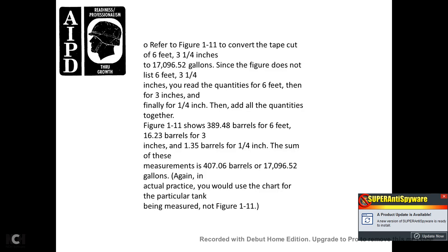Refer to Figure 1-11. Convert the tape cut of 6 feet 3 and one-quarter inches. Since the figure does not list 6 feet 3 and one-quarter inches directly, you need the quantities for 6 feet, 3 inches, and one-quarter inch separately and add them. Figure 1-11 shows 389.48 barrels for 6 feet, 16.23 barrels for 3 inches, and 1.35 barrels for one-quarter inch. The sum is 407.06 barrels or 17,096.52 gallons. In actual practice, use the chart for the particular tank being measured, not Figure 1-11.